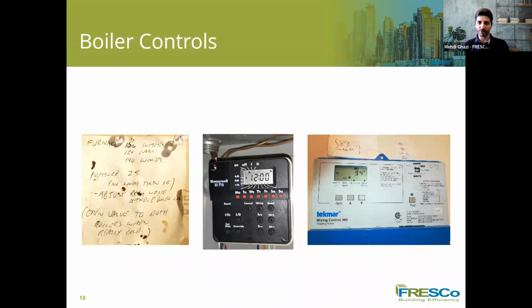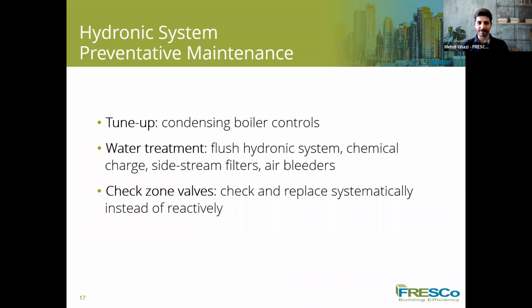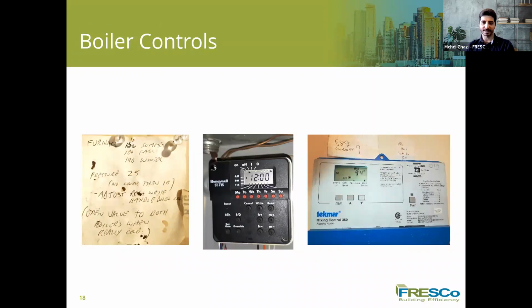The middle photo shows a control system which is not set up correctly. It's stuck, fixed at 12, clearly not functioning. We see this usually on analog timers, but sometimes it happens on digital ones also. It's always good to check if our control system is working properly or not, and if the on and off set points are adjusted and working properly, and we need to make sure that our control systems are performing well.